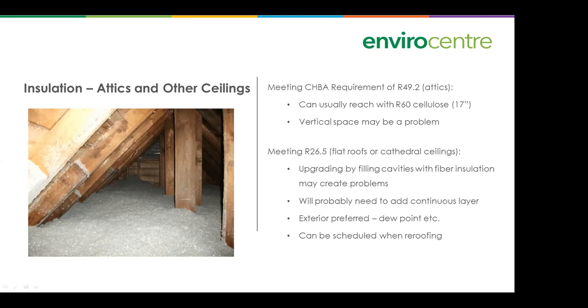If you have framed cavities - typically 2x10s, or some larger dimension like 2x12s or maybe even 2x8s up under the flat roof - you could fill those cavities with more fiber insulation, but that may create problems if you ever have water leaks, or create problems for venting and so on. So a better approach may be to add a continuous layer on the rooftop on the exterior, which would be preferred to deal with the dew point situation, etc. But that could be scheduled when re-roofing. If you're going to be doing re-roofing, it could be a great opportunity to make the outer layer define your building envelope.